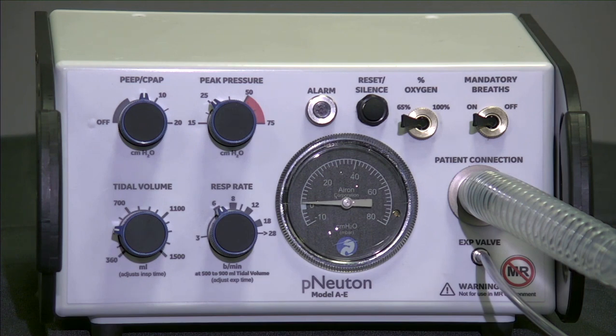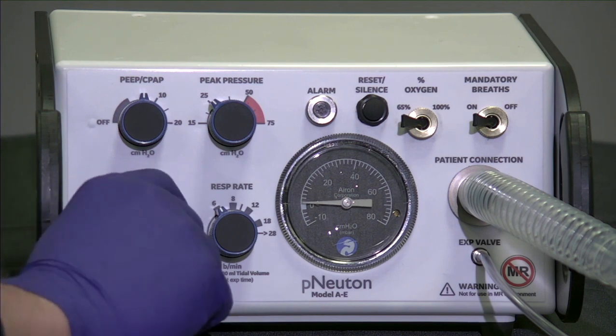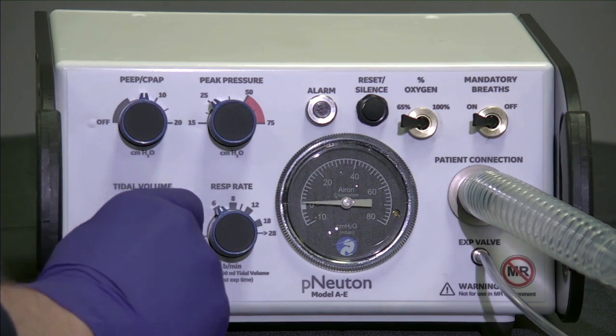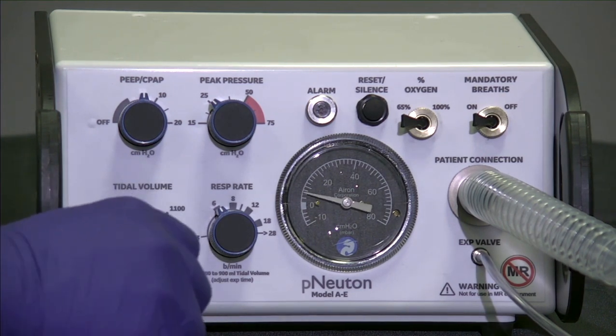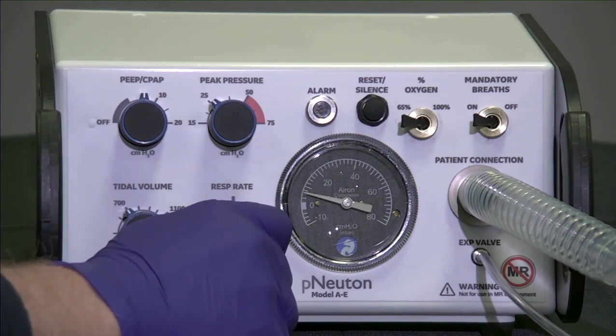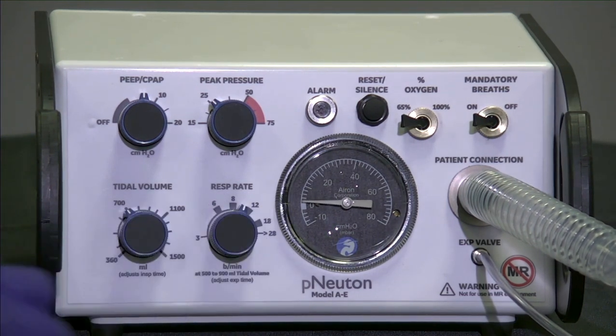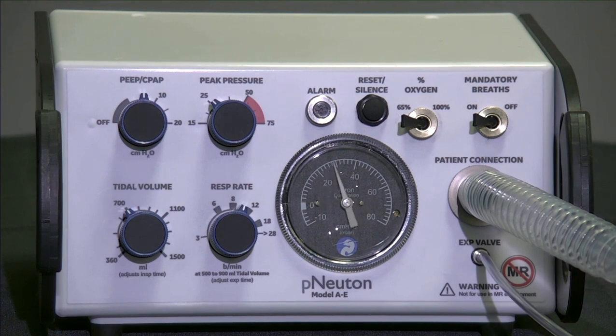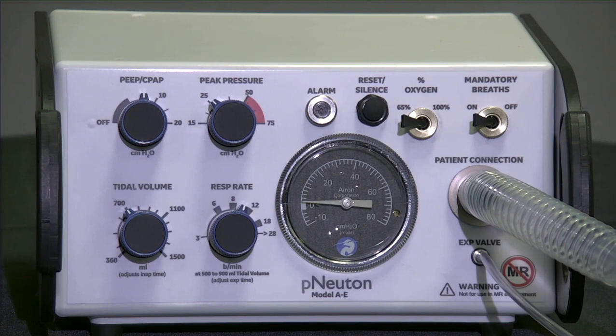Next, let's discuss patient setup using tidal volume and respiratory rate controls. Set the desired patient tidal volume between 360 and 1500 milliliters and the respiratory rate between 3 and 28 breaths per minute or greater. With a preset peak flow, when you change the tidal volume, your inspiratory time changes. Changing the respiratory rate changes the expiratory time. It is recommended that the clinician always monitor the mandatory respiratory rate. For further information on the interaction of tidal volume and respiratory rate, please refer to your user's manual.